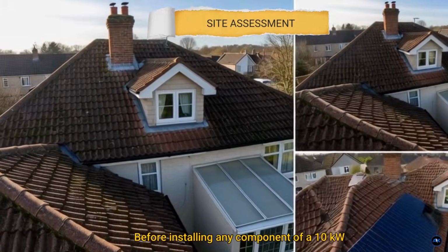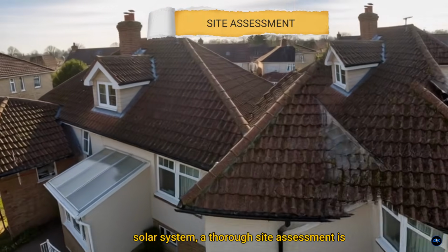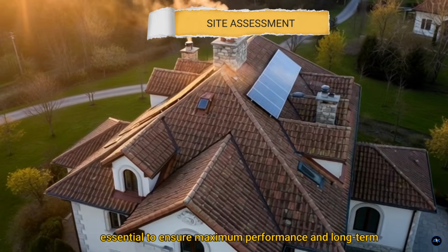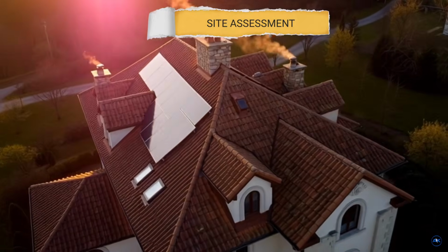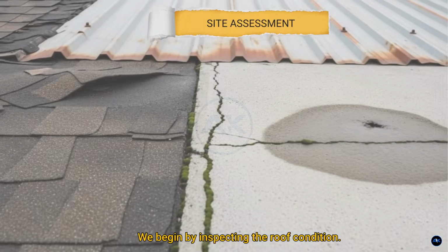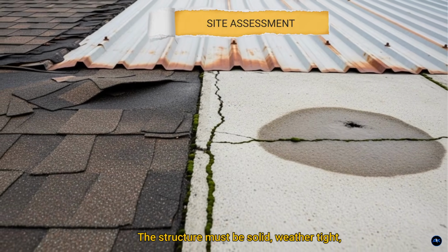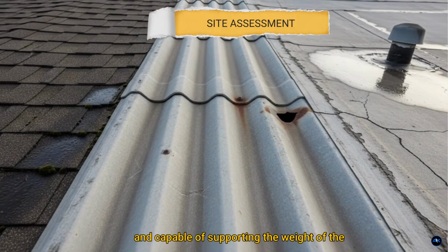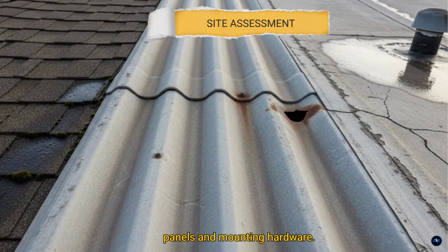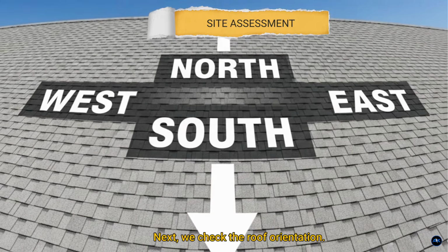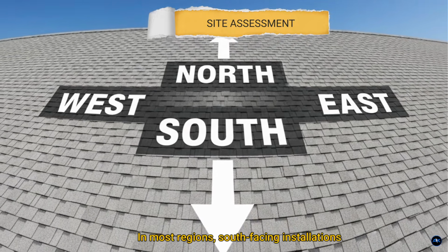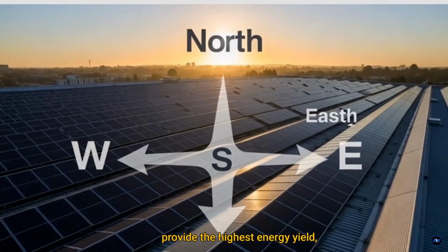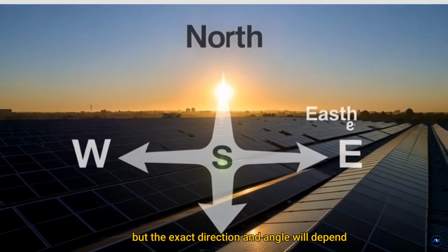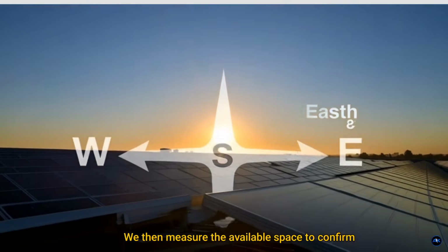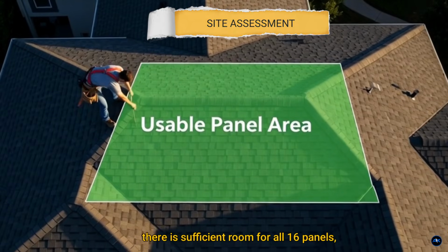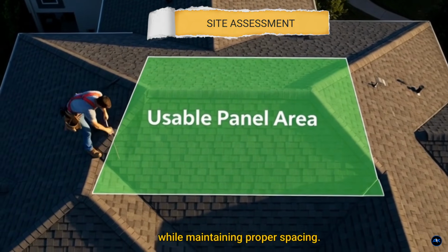Before installing any component of a 10 kilowatt solar system, a thorough site assessment is essential to ensure maximum performance and long-term reliability. We begin by inspecting the roof condition. The structure must be solid, weather-tight, and capable of supporting the weight of the panels and mounting hardware. Next, we check the roof orientation. In most regions, south-facing installations provide the highest energy yield, but the exact direction and angle will depend on your location.